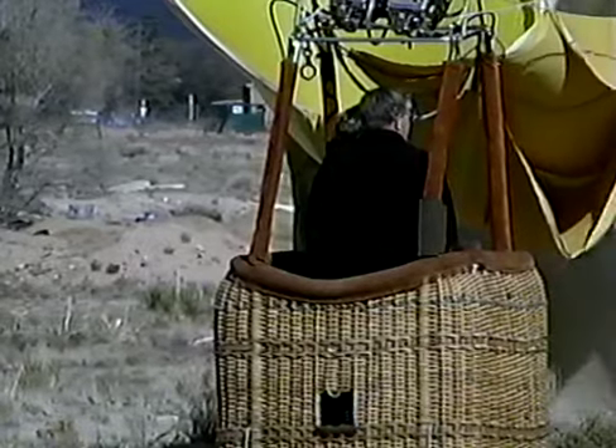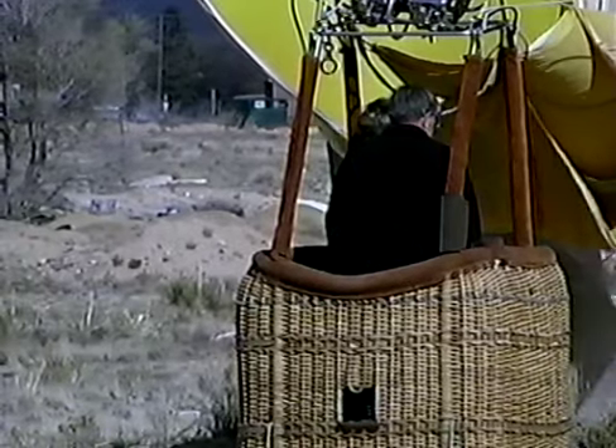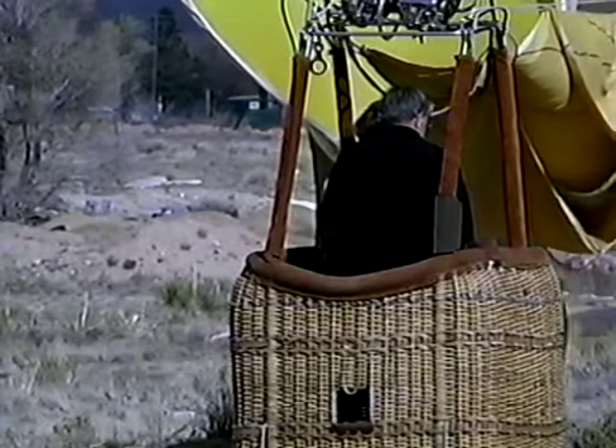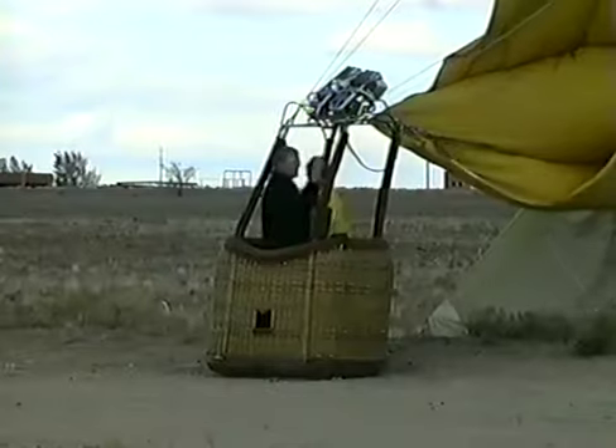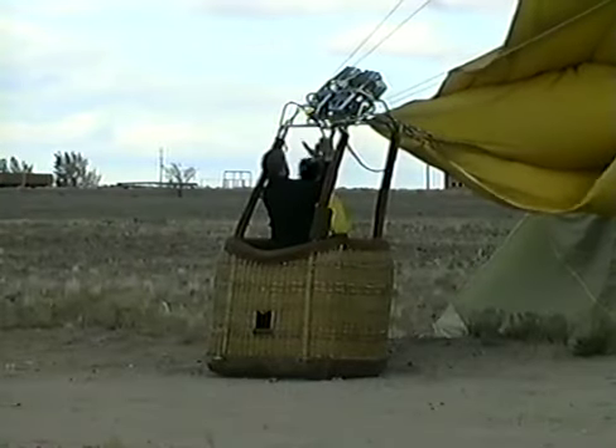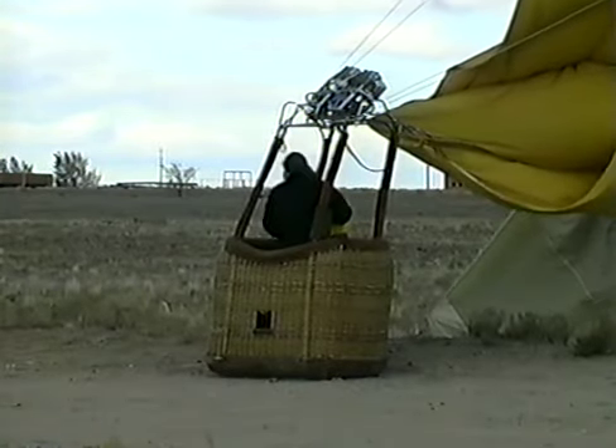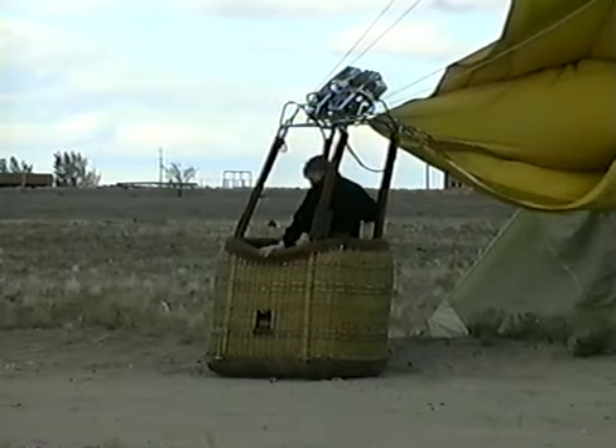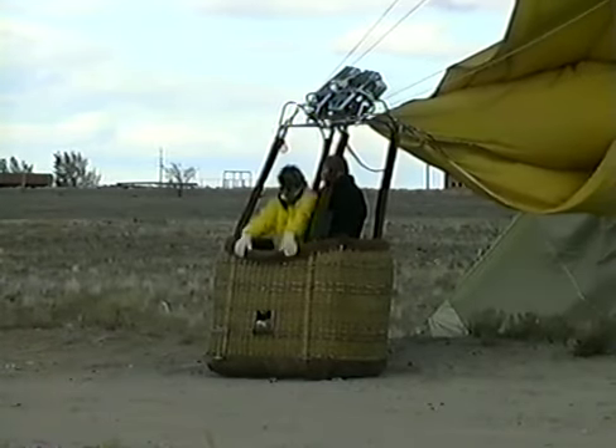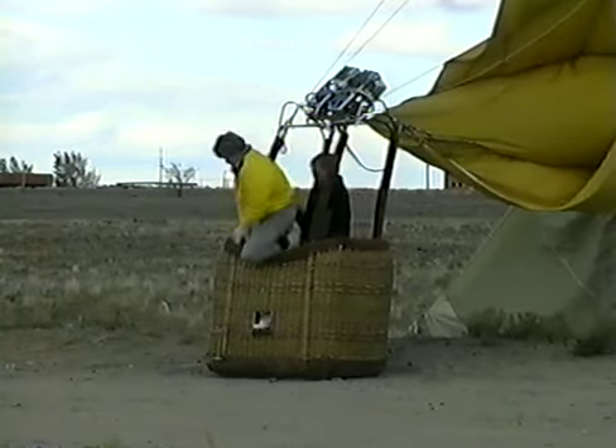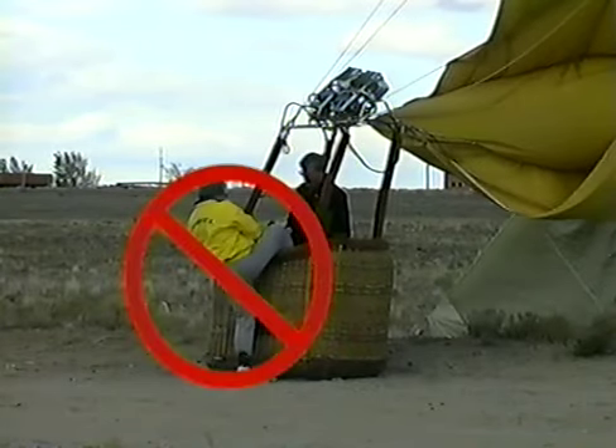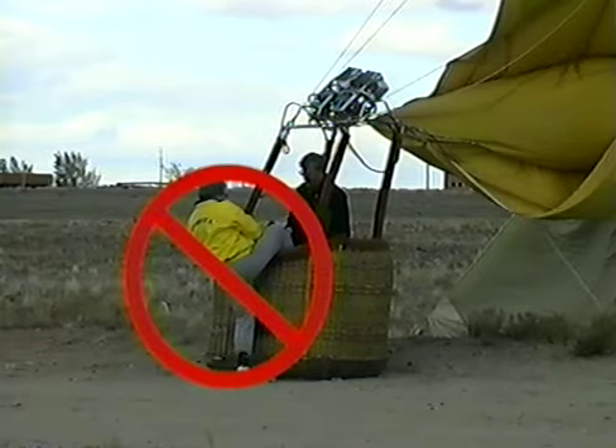Let's look at the effect of step voltage when leaving the basket and what to do to exit and clear it as safely as possible. Initially, when leaving an energized basket, make sure to jump completely clear of it and avoid touching any part of the balloon system and the ground at the same time. If any part of your body touches the balloon, you'll complete the electrical circuit and become the conductor to the ground. You will be instantly injured, maybe even killed.